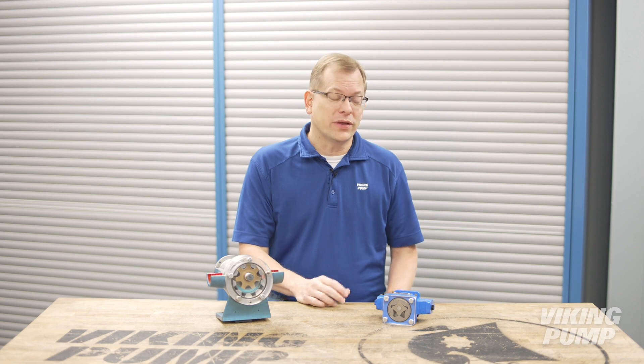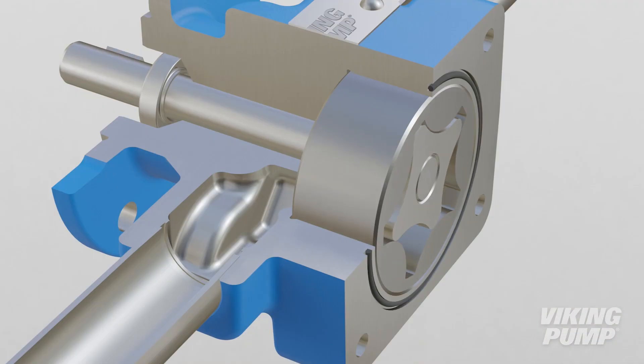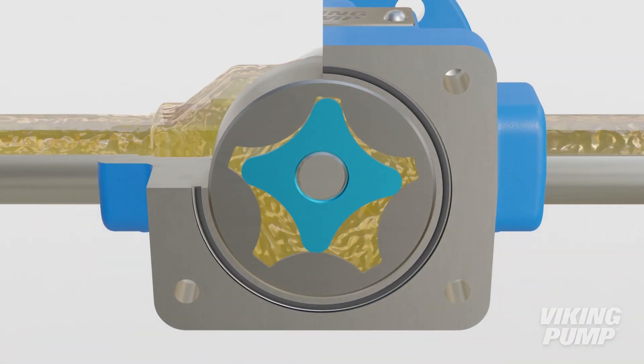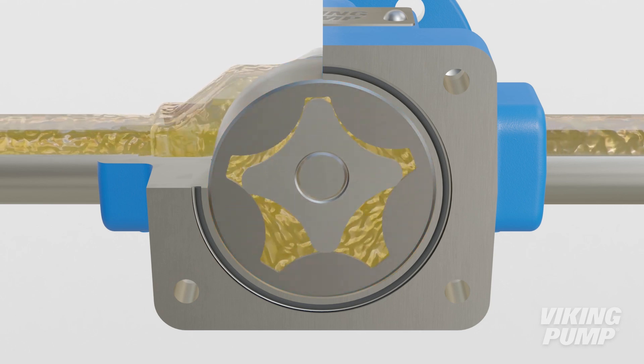It's still a type of internal gear pump with its gear-within-a-gear design, but these pumps are more commonly referred to as gerotor pumps. Unlike a traditional internal gear pump where the outer rotor gear is the driver, a gerotor is driven by the inner pumping element. It has one fewer tooth than the outer element, creating the offset and pumping cavities.